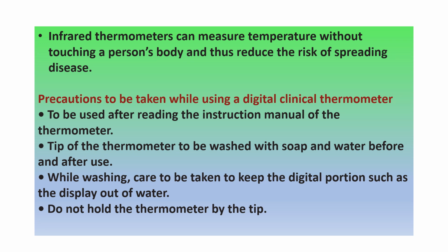Then the tip of the thermometer should be washed with soap and water before and after use. This is the second point: we have to use soap and water to wash the tip of the thermometer, before and after use. Third point is that while washing, care has to be taken that the digital portion, the display, should be kept out of the water. And we should not hold the thermometer by the tip.